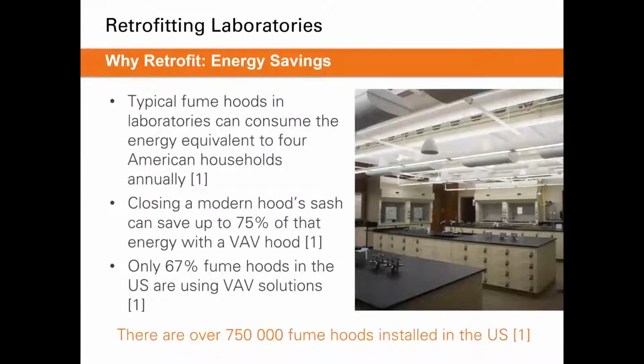This seems like a very large number, but if you think about fume hoods and how they themselves require a lot of ventilation in order to maintain safe containment, and all of that air isn't being recirculated back into the lab, it's being dumped directly outside. So because these fume hoods require so much air to maintain safety, and because the space itself needs to be tempered and the temperature controlled for the comfort of the lab users, all of that energy that's being put into tempering the space that the hood just dumps directly outside is directly related to the energy usage of the fume hood. So that's where that number can come from, of it equaling up to 4 American households annually in energy consumption.